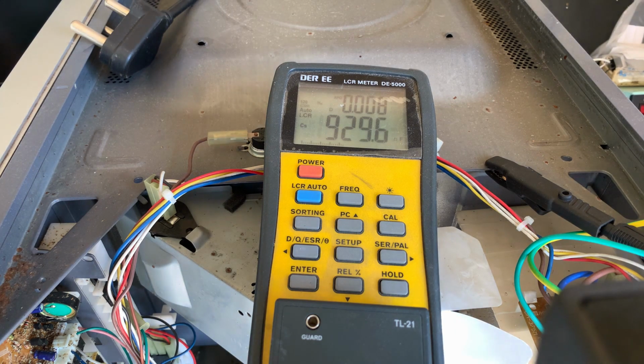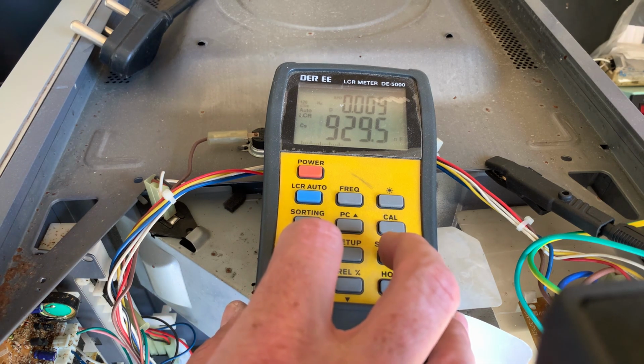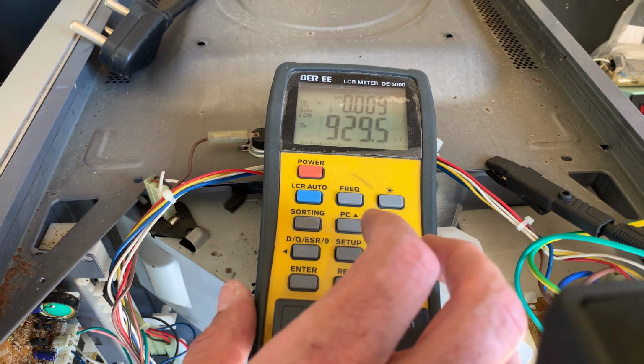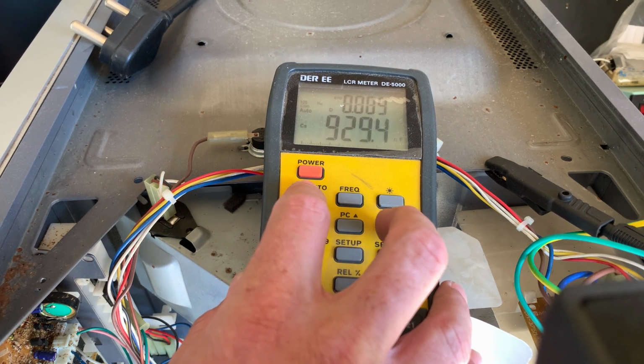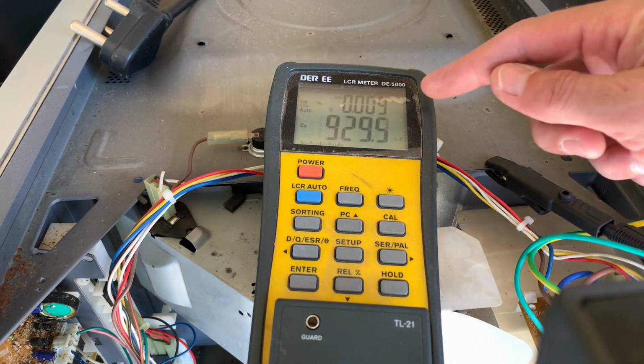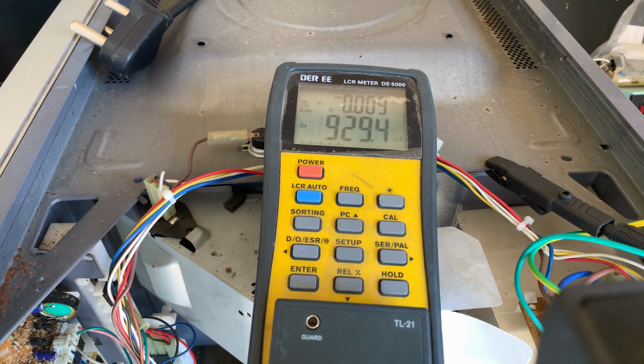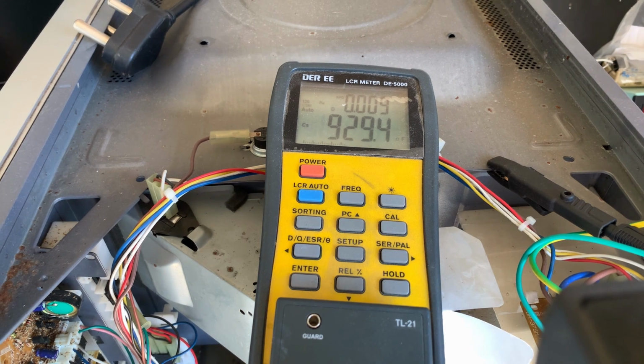So if we now go and look at the capacitance, we can see it's 929 nanofarad, so it's 0.92 microfarad. And what is interesting, let's do this. The dissipation factor is 0.009. I did find a data sheet on that specific capacitor. That capacitor, typically they say the dissipation factor must be less than 0.01, so we are actually okay. So that capacitor is fine. So my suspicions of that capacitor were unfounded.